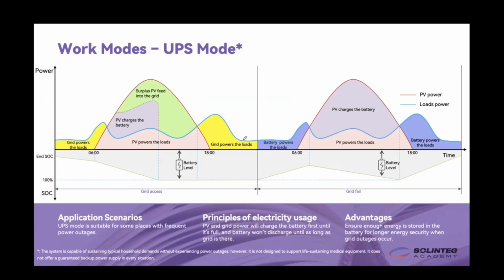As we can see from the diagram over here, when the grid is still in this system, at nighttime the grid will power the loads, and at daytime the PV and the grid will support the load together, but they will first make sure that the battery is fully charged. After that, at nighttime, when the PV doesn't generate power, the grid will support the load. And if the grid has failed, during the nighttime the battery will power the load, and during the daytime the PV will generate power to support the load and also charge the battery. At nighttime, again, the battery will power the load.